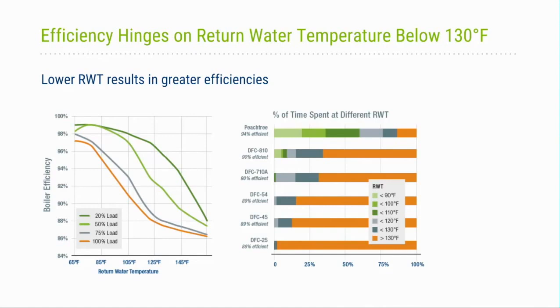And so what this is capturing is that there's a pretty wide range in the buildings we evaluated of how well they're doing at returning the water back to the boilers at a point where the system is really going to function highly efficiently and provide that condensing aspect. At the bottom, the DFC building number 25, most of the time we were actually getting return water temps above 130 back. And so, yeah, it's still a nice high efficient boiler, but you aren't getting all of the benefits of condensing. Whereas building 710 and 810, they were doing a much better job at getting lower return water temperatures. And then the Peachtree was doing a really good job.